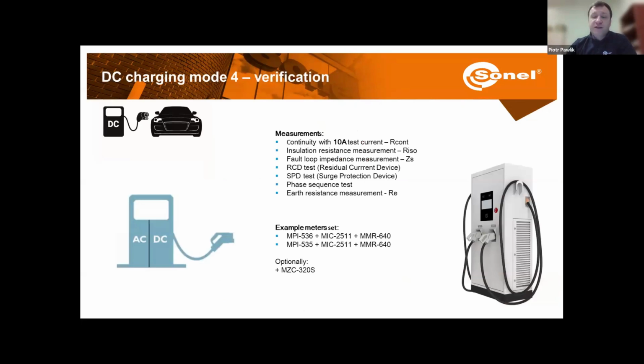Here we need to check its continuity, insulation resistance, and the coding resistor. And finally, for the DC charging station, we need to remember that the charging station is connected to the AC grid. So the DC charging stations have the AC part and the DC part. For that reason, we need to check fault loop impedance, insulation resistance, RCDs, and phase sequence test. We need to check continuity here with 10 amps test current. And on the DC charging stations, we are going to have surge protection devices, which we also need to test. And in case the station has its own earthing, we will also need to check earth resistance. All right, so these are different measurements for different types of stations.